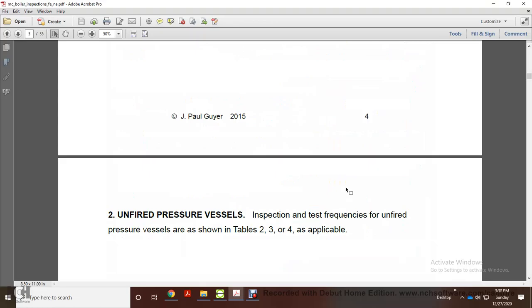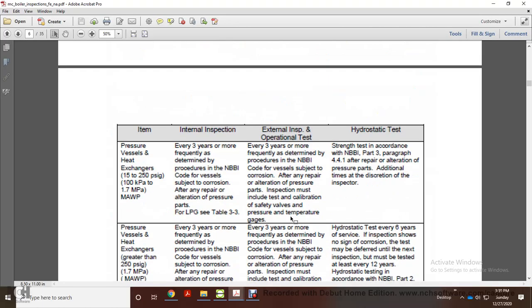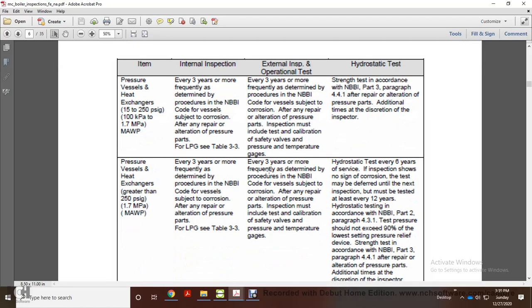Alright, number 2. Unfired pressure vessels. Inspection and testing frequencies for unfired pressure vessels are shown in Tables 2, 3, and 4, as applicable. Pressure vessels and heat exchangers at 15 to 250 psi gauge maximum allowable working pressure: internal inspection every 3 years, or as determined by the NBBI code for vessels subject to corrosion, and after any repairs or alteration of pressure parts. External operation and testing check every 3 years, or more frequently as determined by procedure in the NBBI code for vessels subject to corrosion, after any repair or alteration of pressure parts. Inspection includes testing and calibration of safety valves, pressure gauges, and temperature gauges. Hydrostatic test and strength test according to the NBBI Part 3, paragraph 4.4.1, after repair or alteration of pressure parts, and at additional times at the discretion of the inspector.